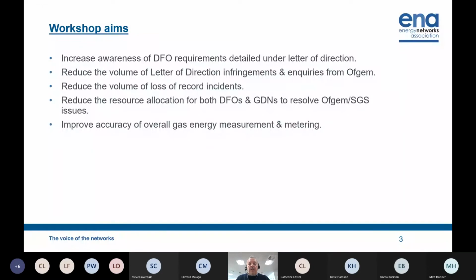Reducing the volume of loss of record incidents is a primary focus as well, because a lot of these SGS issues result in the GDNs raising a loss of record incident with National Grid, which ultimately can lead to a reduction of the CV for the whole LDZ. Also, loss of record incidents within the D+5 window can result in increases in National Grid CV shrinkage, which is ultimately paid for by gas shippers who operate on the transmission system, and then that flows through to customers.